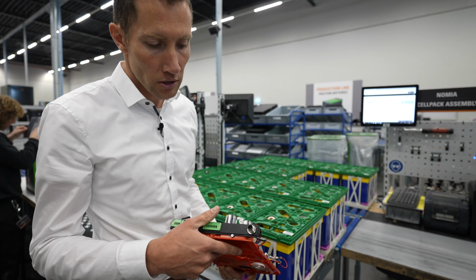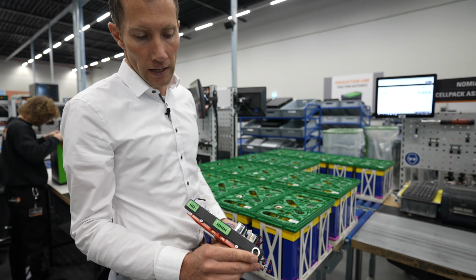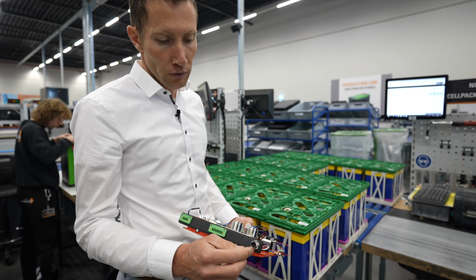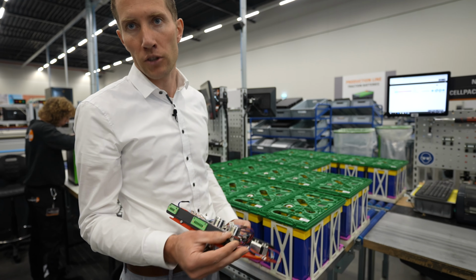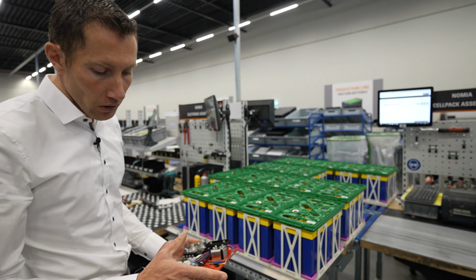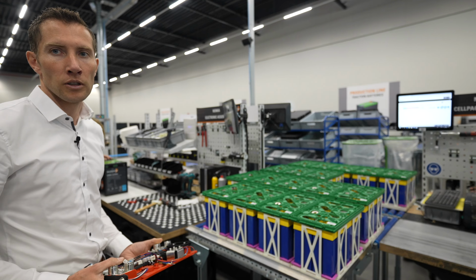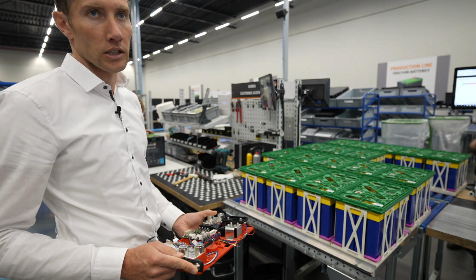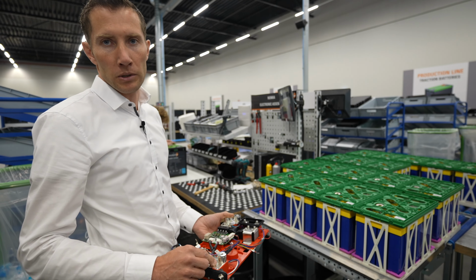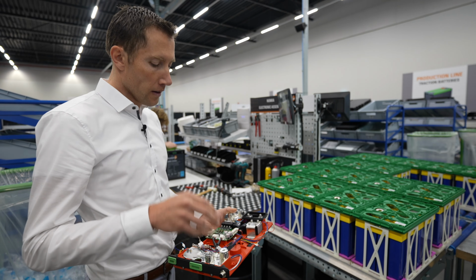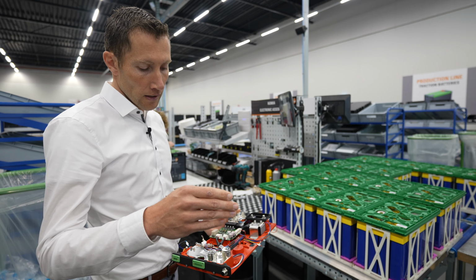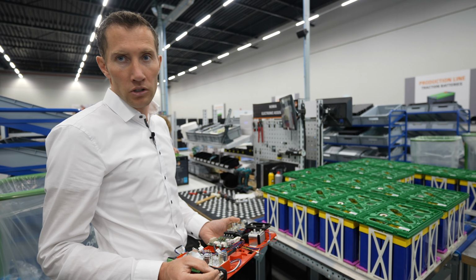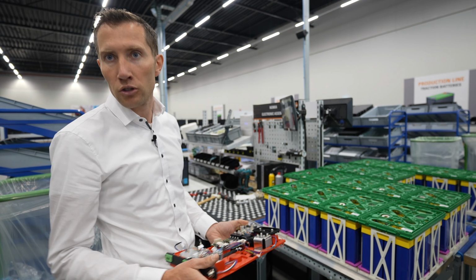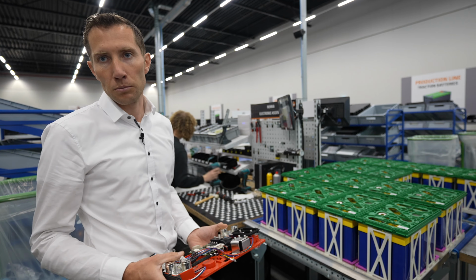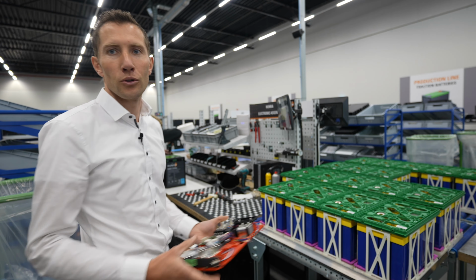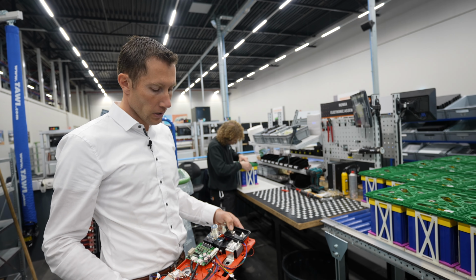Then the BMS communicates with the charger via the CAN network. When all the batteries are full, it will command the charger, okay, you can now stop charging. That's why communicating with the charger is important, because it will also tell the charger when the battery is at 50%, it will ask for the full charge current. When the battery is already almost full, it will tell the charger, I now want to get only like 2 amps, and the charger needs to provide that. It needs to know, that's why you want to have proper communication.